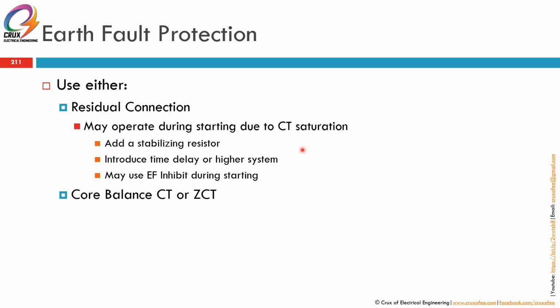So if you're using earth fault with a summation CT or residual connection type CT for the earth fault detection, the earth fault may nuisancely operate due to CT saturation. So what you can do is you can add a stabilizing resistor, or you can introduce a time delay or a higher setting, or you can just use a relay that inhibits the earth fault during starting.